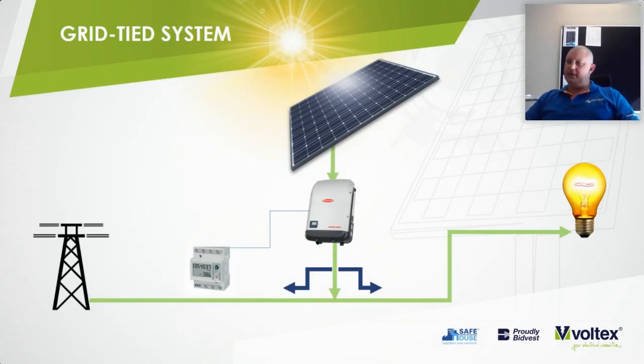Now, the energy meter measures what is coming into the system, and it's got communication with your grid tie inverter. So it throttles the inverter to cater purely for the loads, and not all the excess power is then throttled.